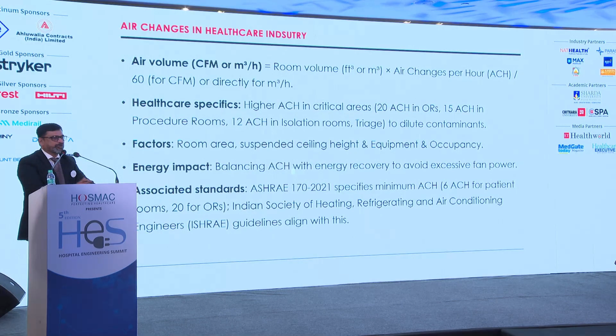So eventually what happens in certain areas, like for example an operation theater of 40 to 45 square meters, 2 to 2.5 ton air conditioner will be sufficient for the cooling required of 21 degrees plus or minus 2. But we cannot do that because we need 20 or 25 air changes. So the load of that particular air conditioner, used as AHU for operation theaters, goes up to 7 tons.